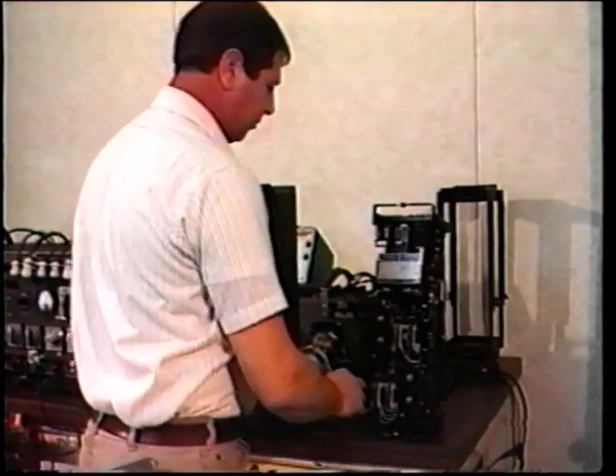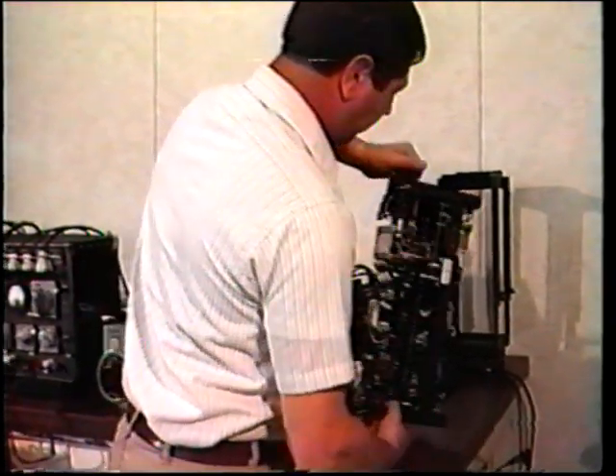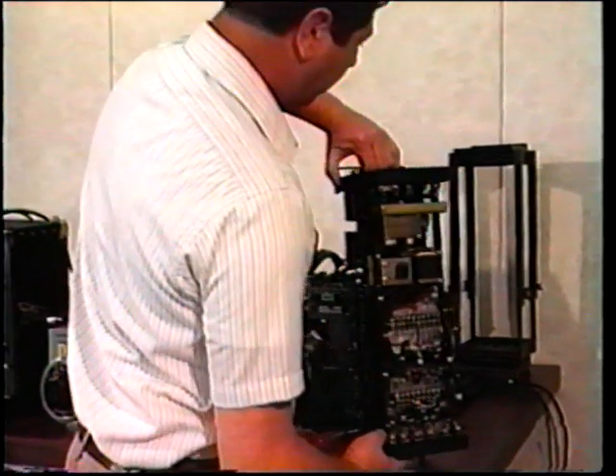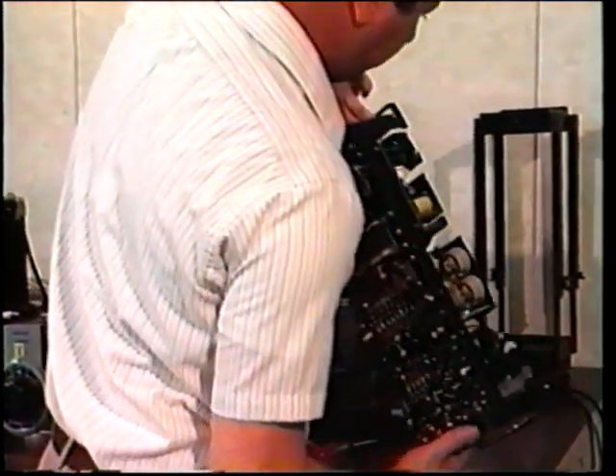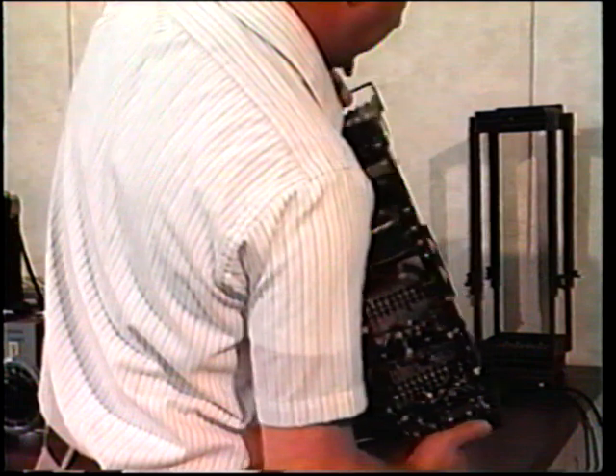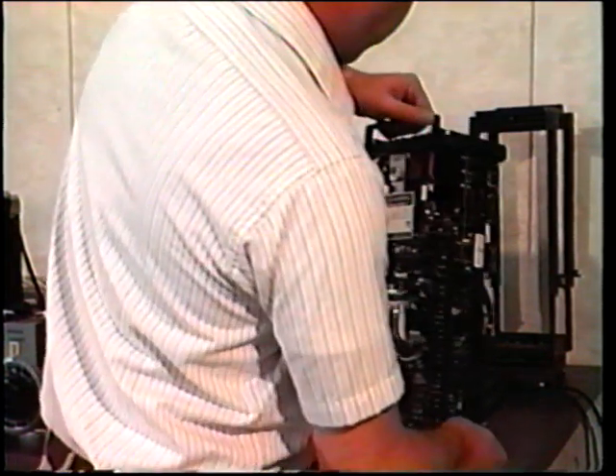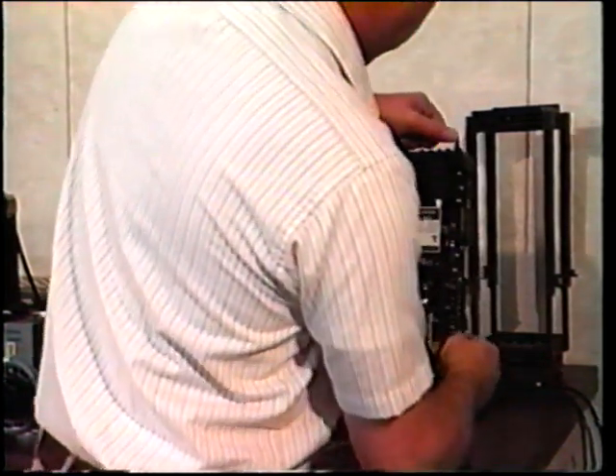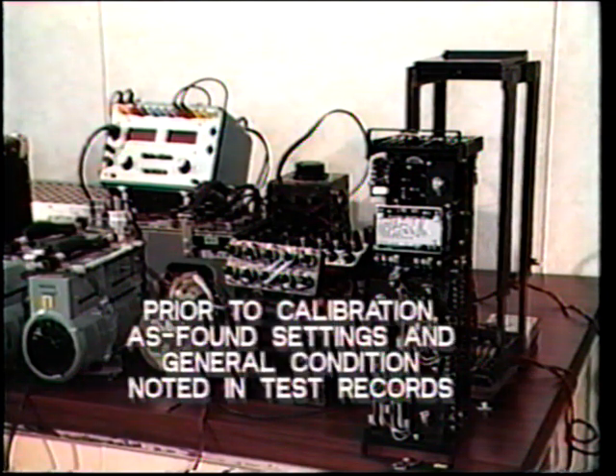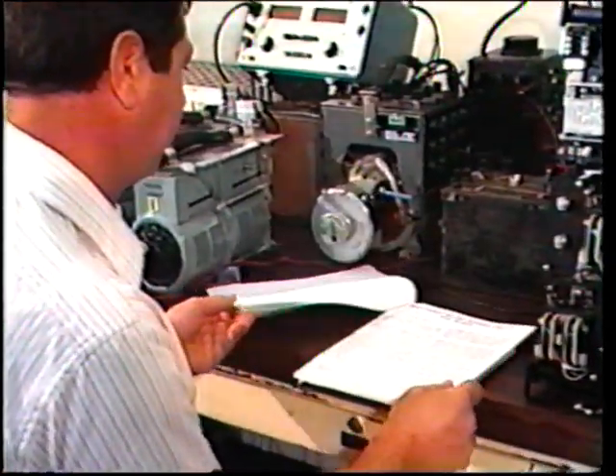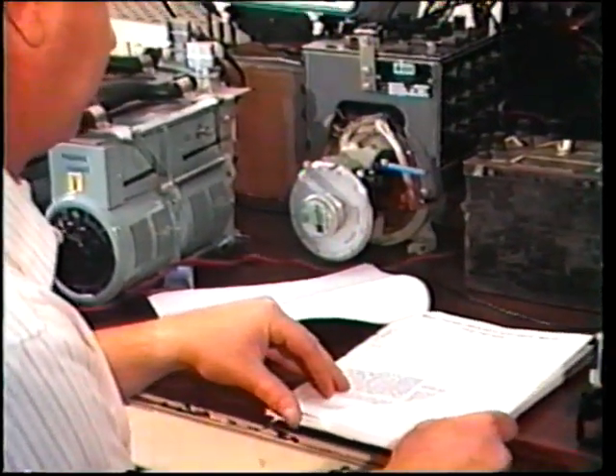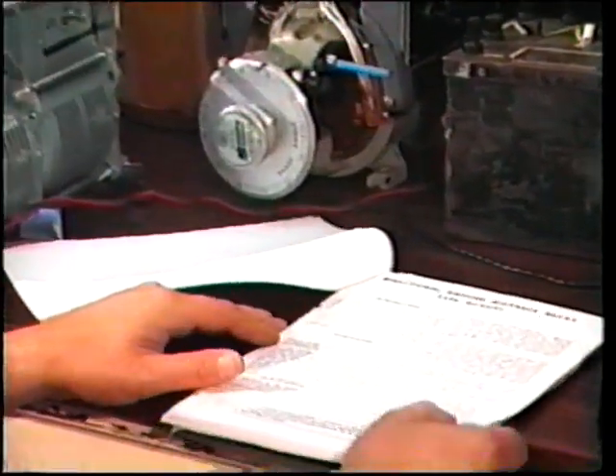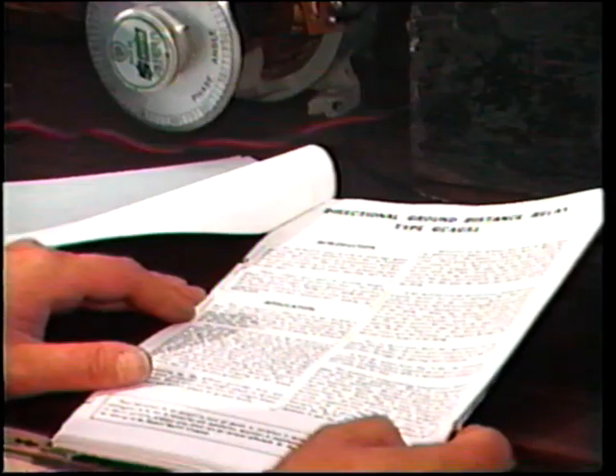The first part of the test consists of the visual and mechanical inspection of all components, including wiring. Check connections for tightness and look out for insulation damage and the presence of dirt or oil. Prior to calibrating the relay, the as-found settings and general condition are noted in the test records. Calibration of each relay must be carried out in accordance with the manufacturer's instructions and specific company operating procedures.